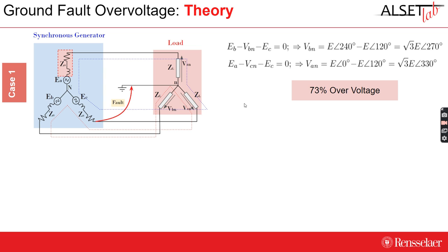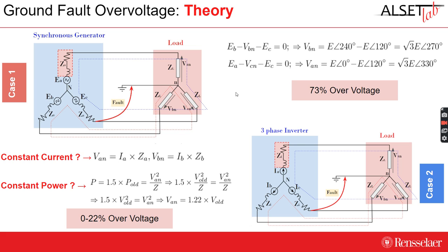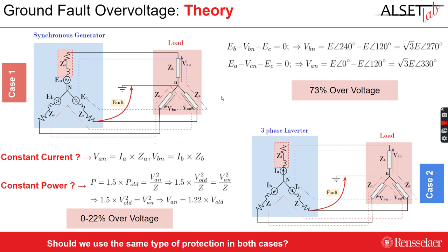However, for inverter-based sources, the situation is different. Since inverter-based sources are sometimes modeled as mostly constant current sources, they should not show any sign of ground-fault overvoltage. Even when we model the inverter-based sources as constant power sources, the ground-fault overvoltage should not exceed 22% theoretically. This gives rise to the question: should we use the same type of protection for both cases?